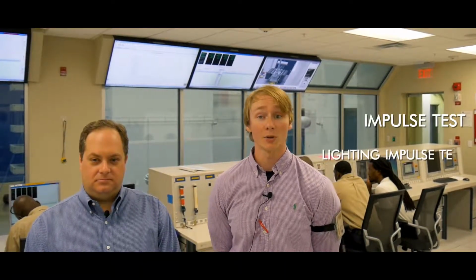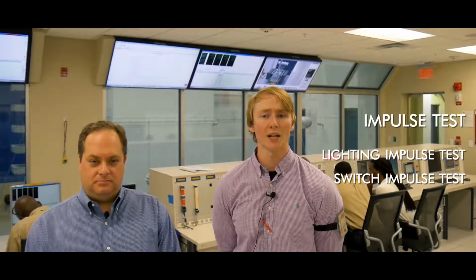After those tests, we have the full capability of doing our impulse test using our 5.2 megavolt impulse generator. These tests include our lightning impulse test and switching impulse test, which are standard for high voltage transformer testing.